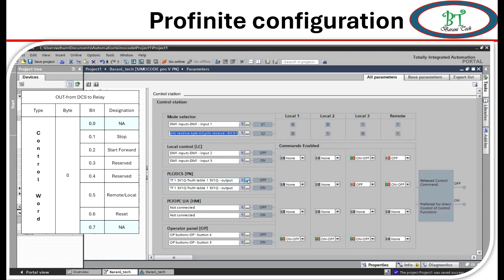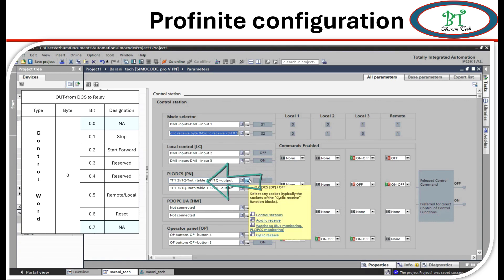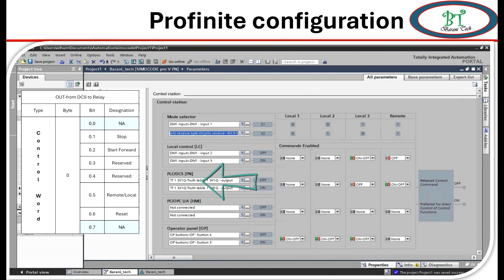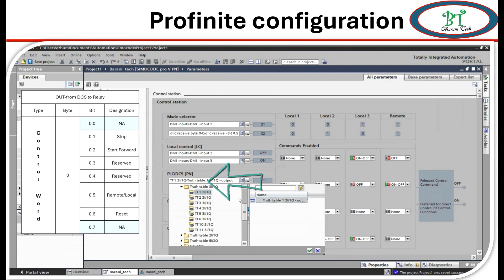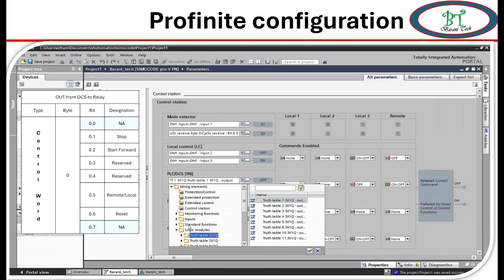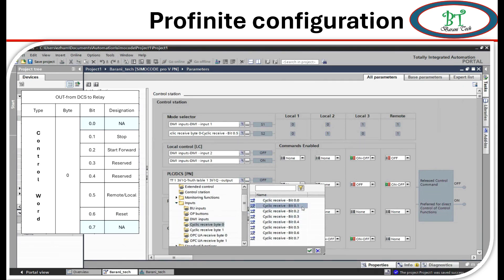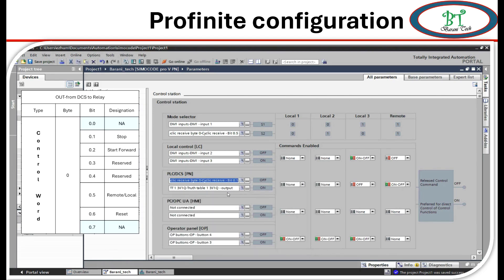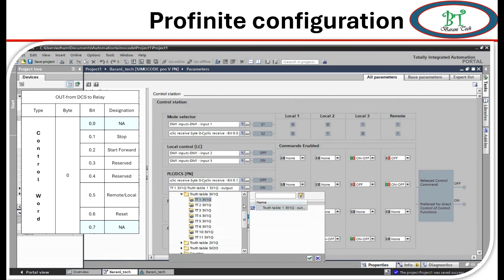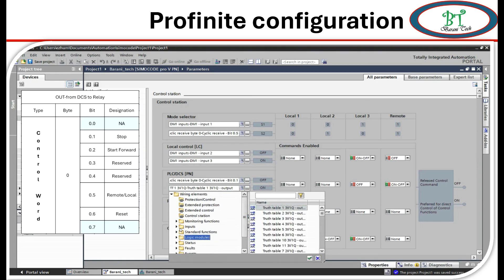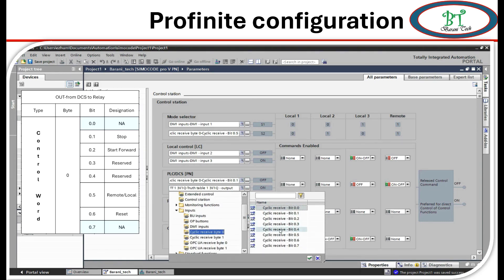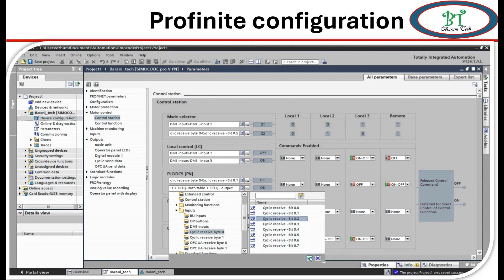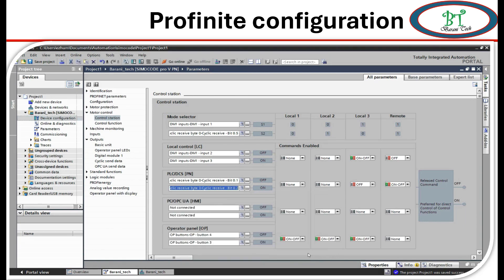Now for remote control on/off, I am going to configure on DCS. For off is the motor stop signal which is cyclic receive bit 0.1. For start, on motor on, the signal is cyclic receive bit 0.2.